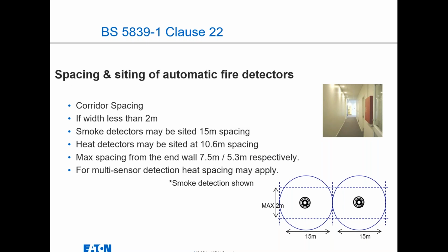So corridor spacing: if the width is less than 2 meters, you can increase that distance from 10.6 to 15 and 7.5 to 10.6 for smokes and heats. But the maximum spacing from the end wall should be back to 7.5 and 5.3. So yes, you can have fewer detectors in the corridor as long as it's no wider than 2 meters, and that reduces some of the costs involved in protecting corridors. And you also need to make sure, if you are using a multi-sensor as a heat only in certain circumstances, that it's considered to be heat spacing, not smoke spacing.